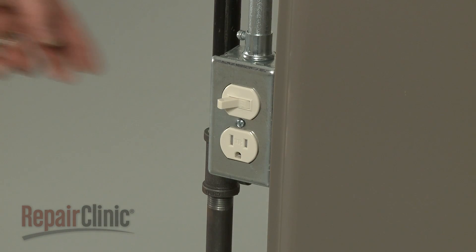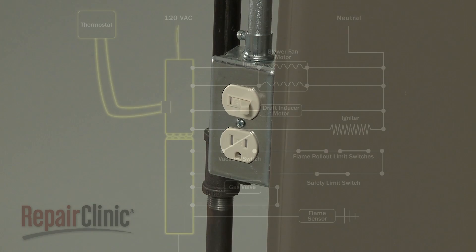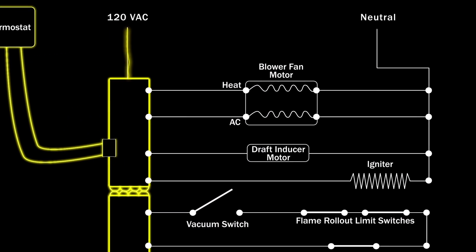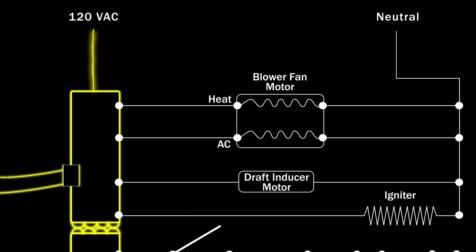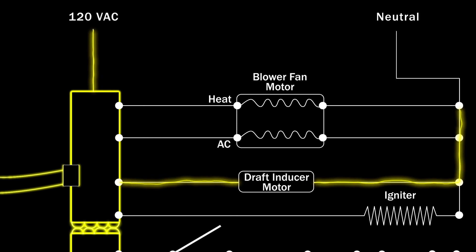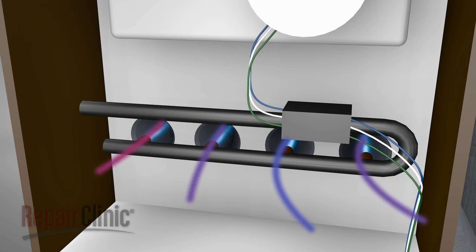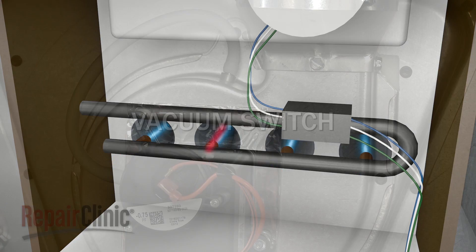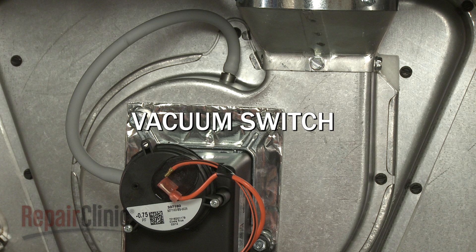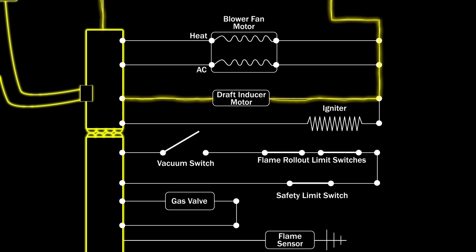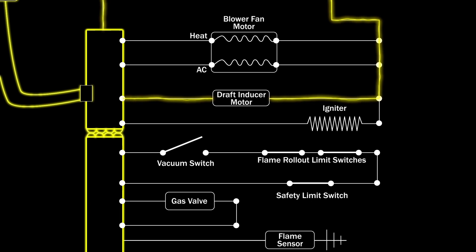This process can be broken down into four main factors: temperature control, ignition, combustion, and air circulation. When the furnace's residential power switch is turned on and heat is needed, the furnace goes through a timed ignition sequence. The sequence begins with the control board sending 120 volts of alternating current to the draft inducer fan motor. The inducer fan motor draws air into the burner assembly, which may be the air surrounding the furnace or fresh outside air supplied by a pipe. Once the fan reaches its maximum speed, a vacuum switch is closed, which ensures that gas will not enter the furnace unless the toxic fumes can be exhausted. If the inducer motor does not turn on or runs too slow, the vacuum switch will not close and the ignition sequence will stall.